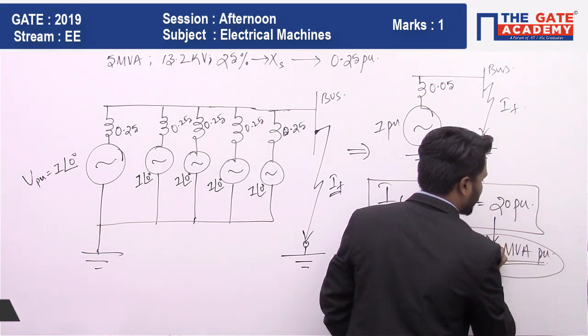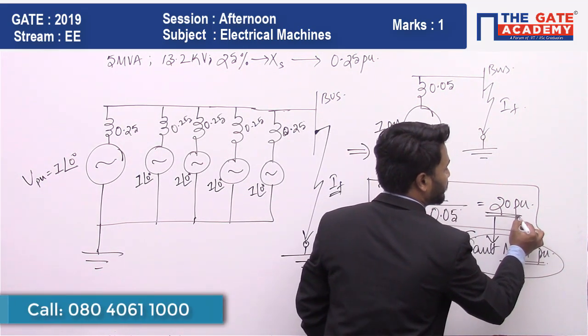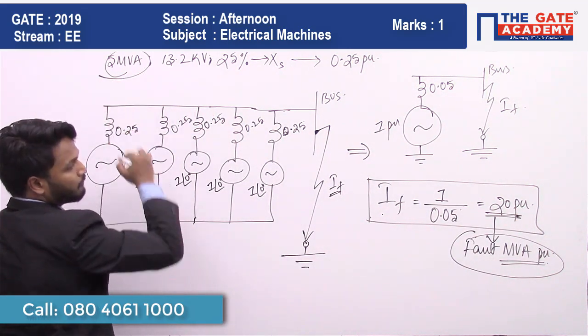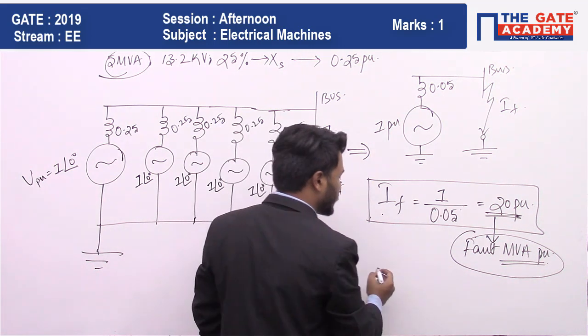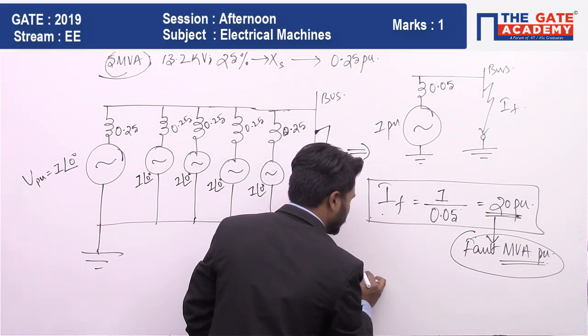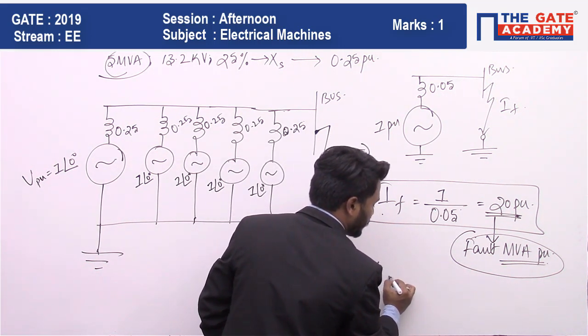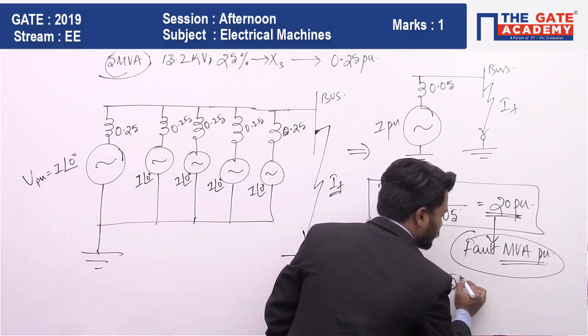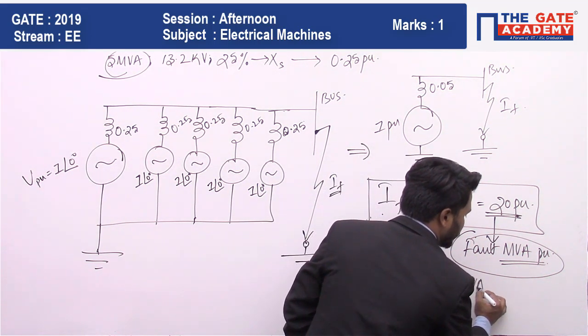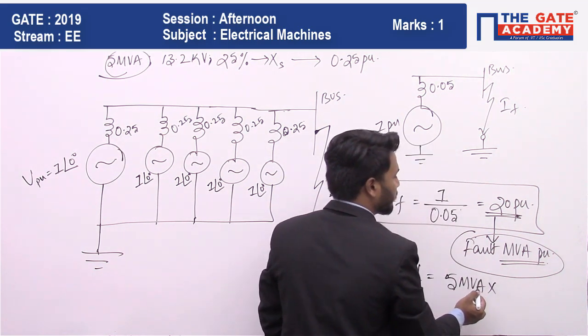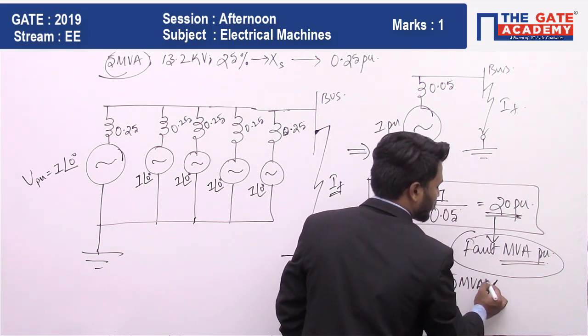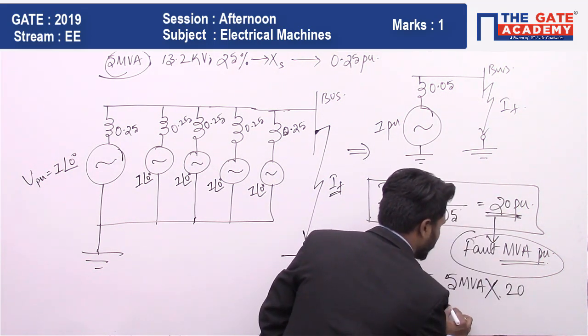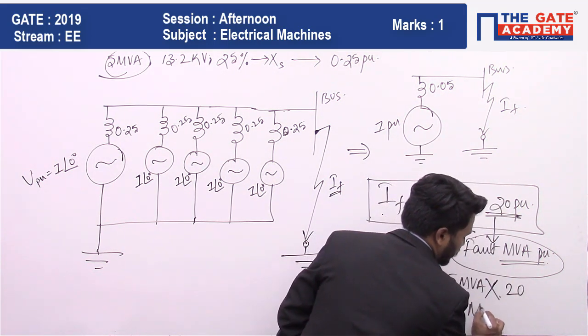Fault MVA per unit—per unit value multiplied by the base value. What is the base value? Base value is 5 MVA. Total fault level in MVA: fault level is equal to base value 5 MVA multiplied by 20, which is going to give 100 MVA.